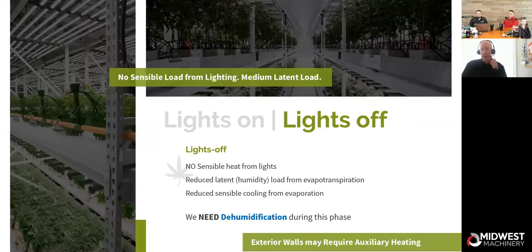I think I mentioned earlier the Penman-Monteith equation, and what we use at Desert Aire for flower rooms is that 75% of the water consumed by the plant occurs in the 12-hour lights on period. And only 25% of the water consumption for the day is transpired during the 12-hour lights off period. So if your engineer made an assumption that, geez, I've got a 24-hour day, I've got this much moisture removed, divide it by 12, and didn't apply the factor that only 25% of it is going to happen in the lights off, you're going to be undersized in your lights on period.